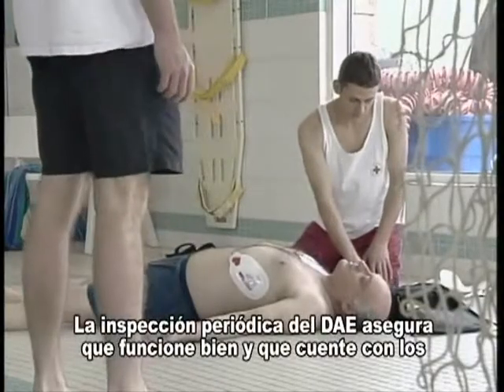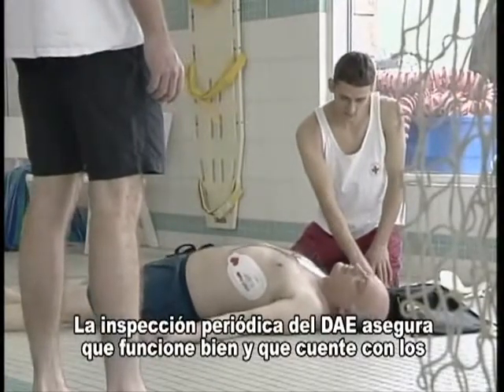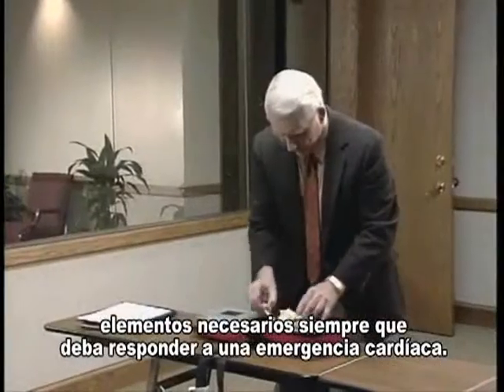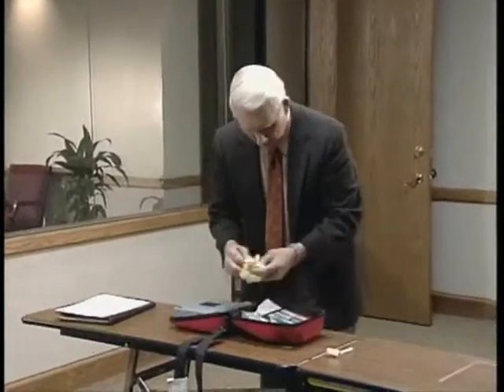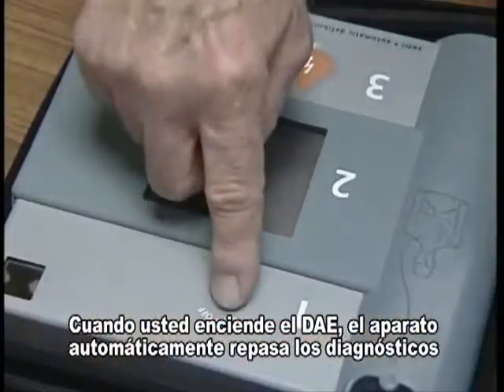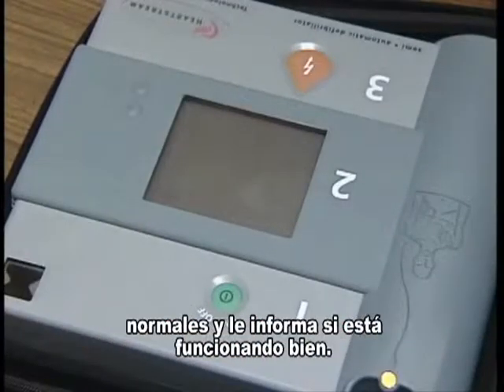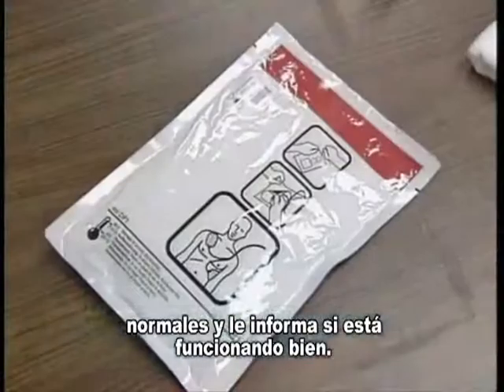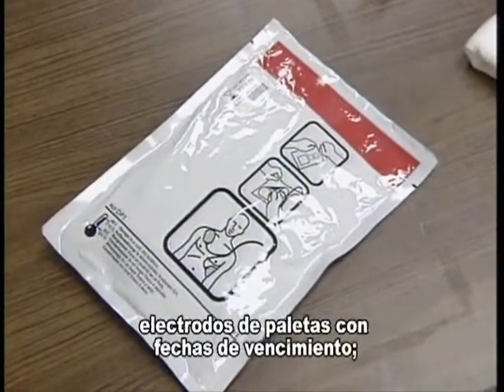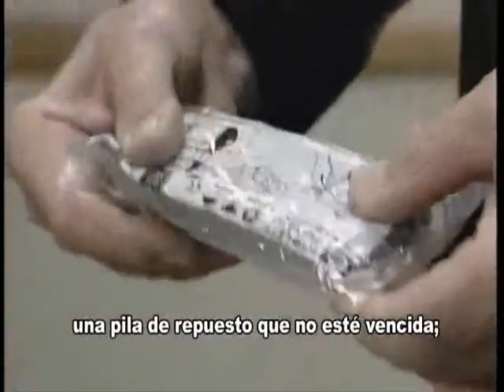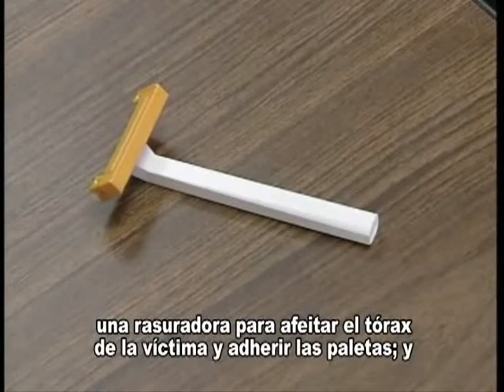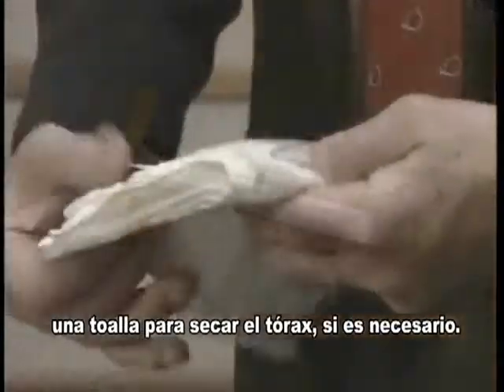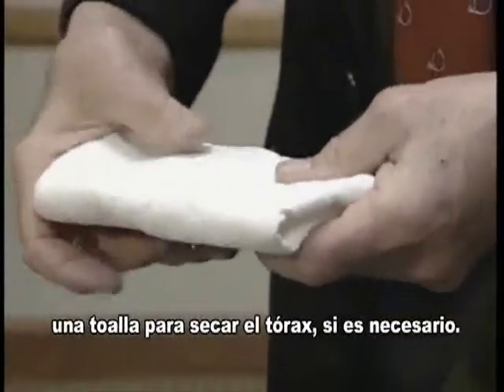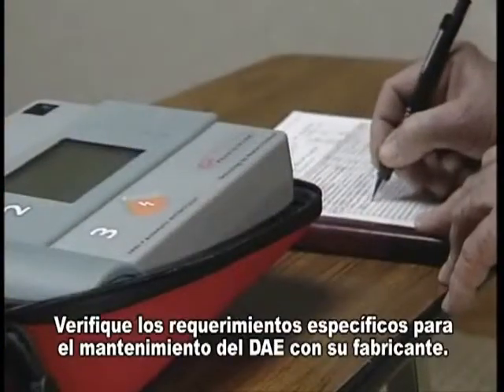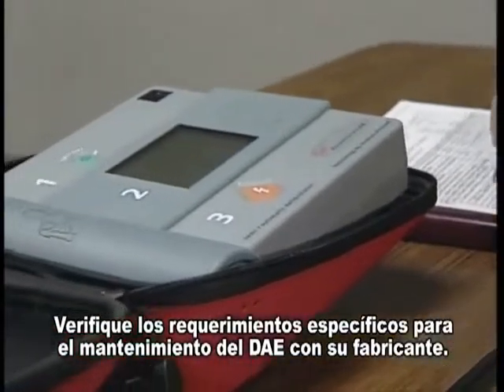Periodic inspection of your AED ensures it will work well and that you'll have the appropriate supplies whenever you need to respond to a cardiac emergency. When you start the AED, it automatically runs through normal diagnostics and informs you if it is functioning properly. Be sure your supplies include electrode pads with unexpired dates, a spare and unexpired battery, a razor for shaving a victim's chest to attach electrode pads, and a towel to dry the chest if necessary. Check with the unit's manufacturer for specific AED maintenance requirements.